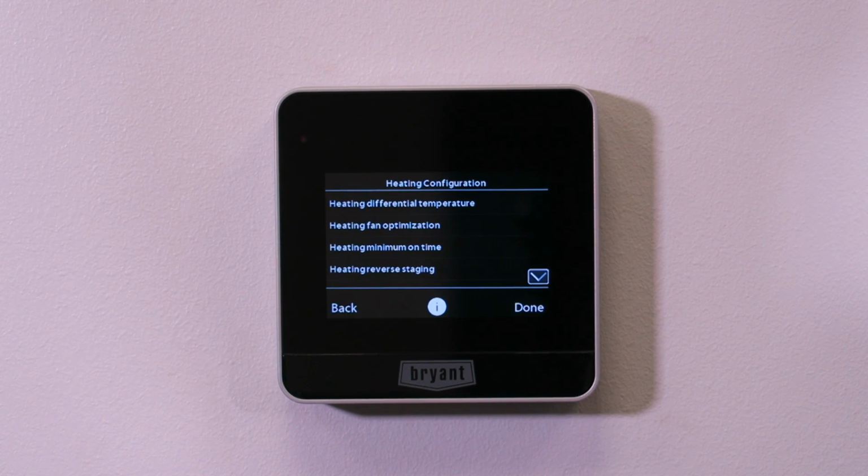What this does is after a heating cycle is over and the gas burner shuts off, I continue to run the fan for, in my case, 90 more seconds. I run the fan, the blower, for 90 seconds, but I shut off the inducer motor, right? The blower motor and the inducer motor are on two sides of the heat exchanger, and they're exchanging energy. If I shut off the one and run the other, whatever residual energy is left in that heat exchanger is mostly going to go the way of the one that's still running the fan, which in this case takes that extra heat in the heat exchanger and puts it into my home, instead of letting more of that heat escape up the flue. So I definitely want to use that.